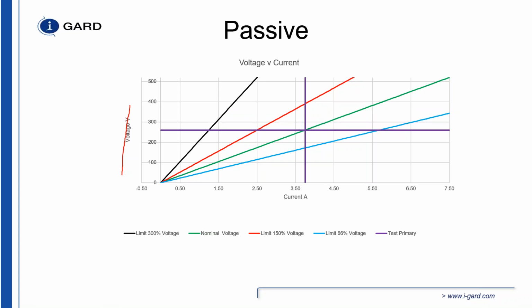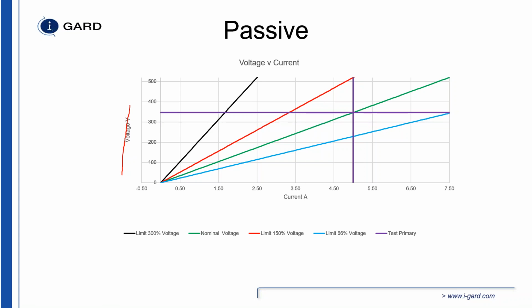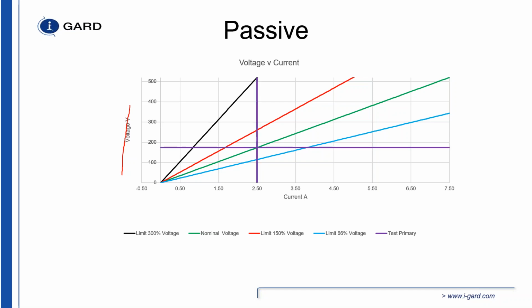At 100% voltage, 100% ground fault, you have 347 volts across that resistor, and you have 5 amps of current on a 600 volt 5 amp system. If you have a 50% fault, you're going to have 174 volts and 2.5 amps. But the resistor is still rated for 69 ohms.